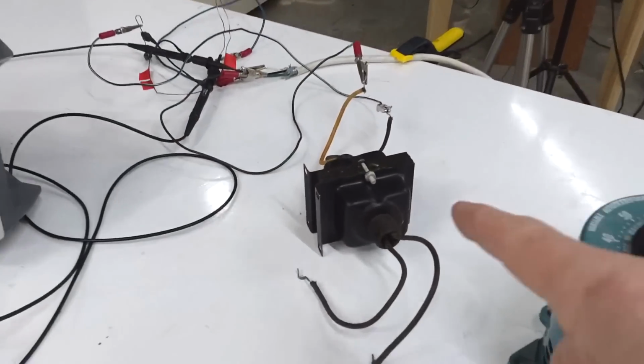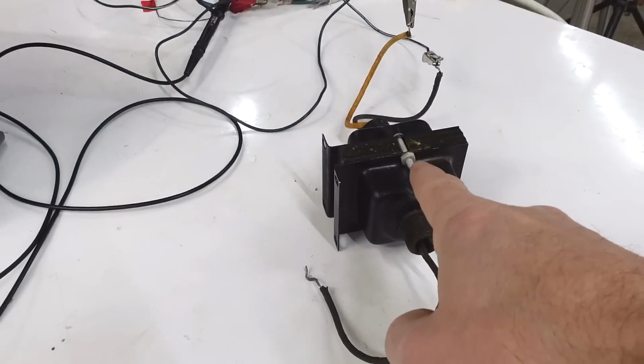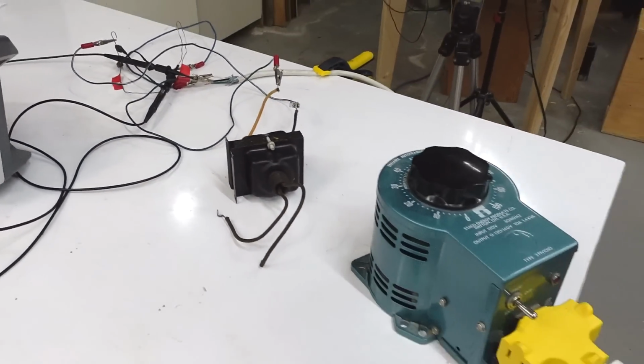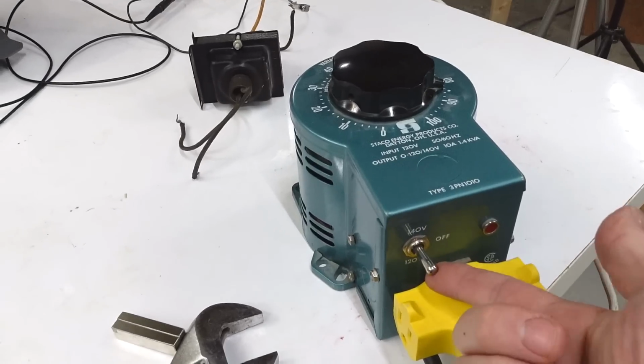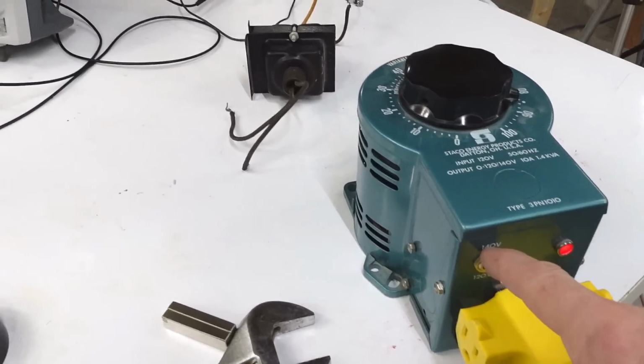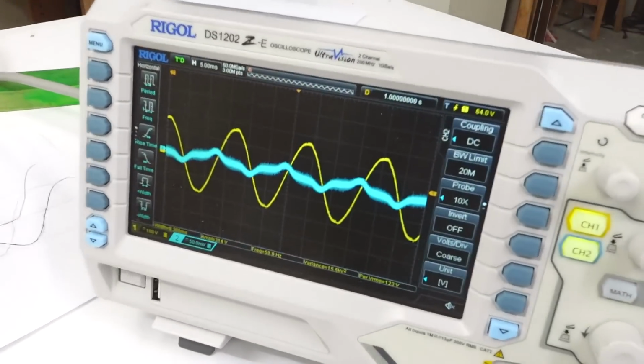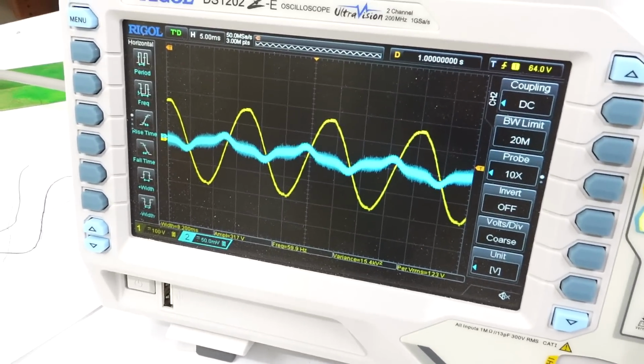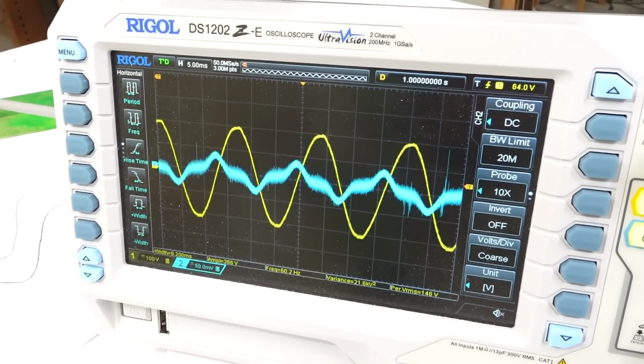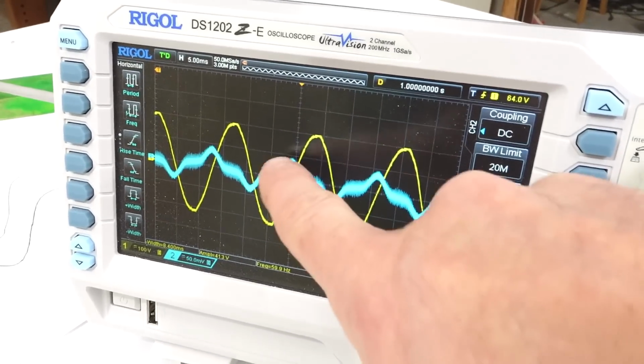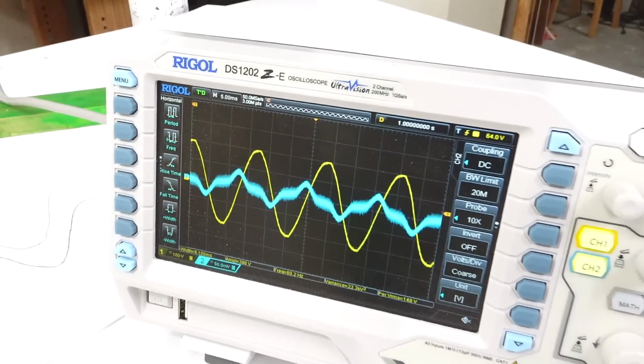Now let's measure the current off of a plain old transformer, but I'm running it through the variac first, which allows me to boost the voltage up to 140 volts. If I look at the waveform here, just by increasing the voltage a little bit, you can see the current waveform gets more bumpy as we're getting closer to saturation of the core.